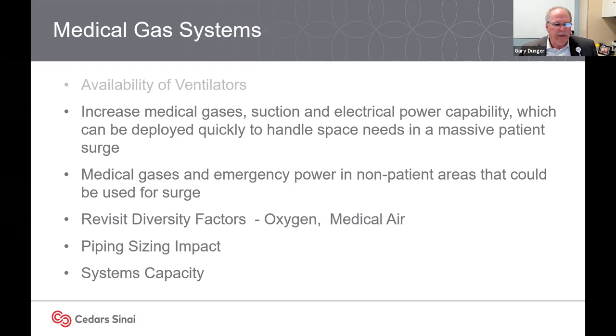We want to rethink the diversity factors for demand considerations for medical gas. Is the pipe size adequate? Is the capacity adequate? Can the piping capacity be increased—can that be done just by increasing the pressure within the pipe? What can the pipe withstand in terms of that pressure increase? What's the maximum safe level, et cetera?